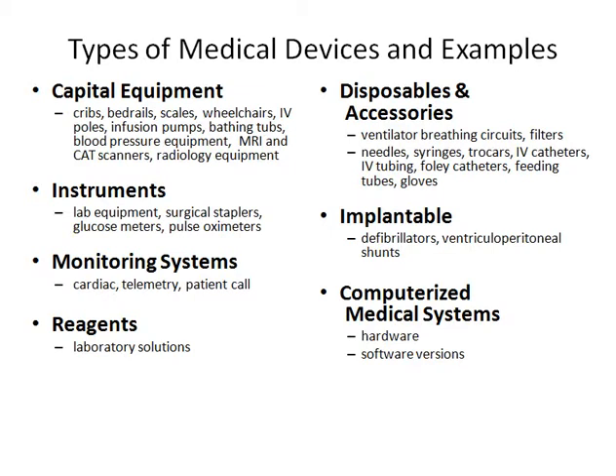For a ventilator, in order to use it, you have to have the patient circuit, right? That patient circuit in Sri Lanka is reusable. When you take a technical spec, we will do a technical spec later. When you do a technical spec in Sri Lanka, they will ask for a reusable patient circuit. If you take a technical spec in Europe, they will ask for a disposable patient circuit. So that cost is high. And when you are working in a private hospital, you can ask for disposable, because you are going to charge that amount from the patient, right? So you can do that, right? So when you're talking about ventilators, there can be bacteria filters that cannot be reused. There are some reusable bacteria filters that are very expensive. So you have to see what is suitable for your hospital, right?